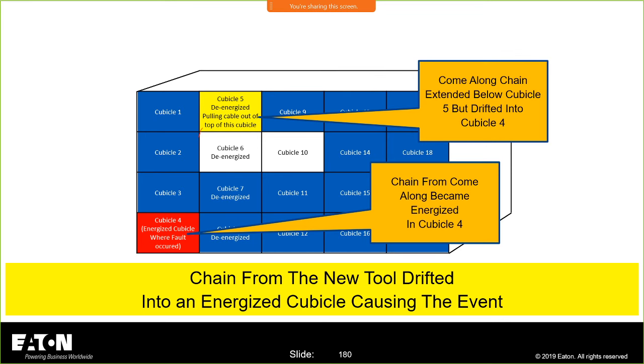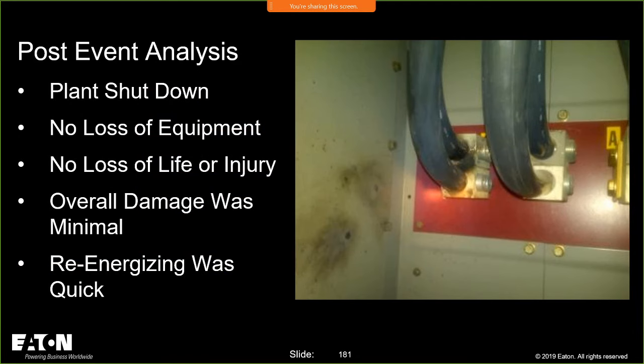But fortunately, the arc reduction maintenance switch took them off without an intentional delay, and the damage to that equipment was little to nothing because they reduced the time. They didn't reduce the current. The current was there. It will always be there because of the impedance of the circuit. But they reduced the clearing time of that overcurrent device, and the damage to the equipment was the size of a dime inside. Right here.